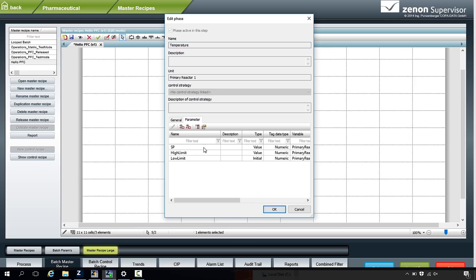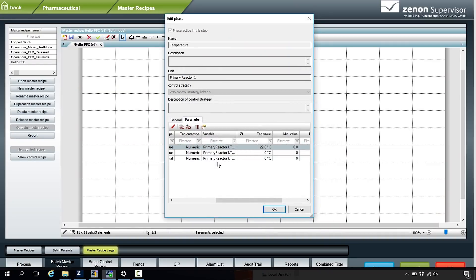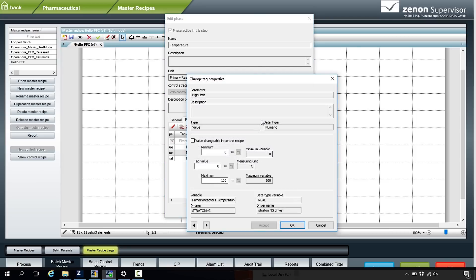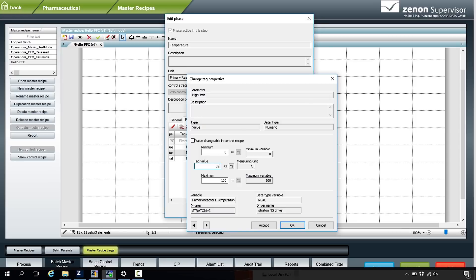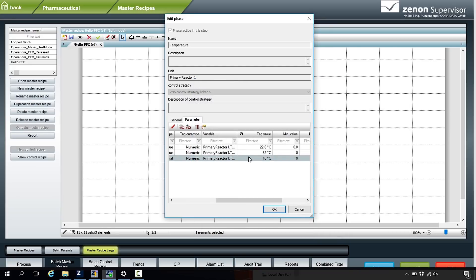We can change the set point — remember, we're looking at temperature here — and we can define a high limit and a low limit. At the moment we have nothing in there, so if we double click, we can give this a value. Let's say 22 degrees. And then the high limit, let's put that at 32. And this one, let's say 10. So we're nice and safe. So we set the control parameters up. This is all configurable at runtime.